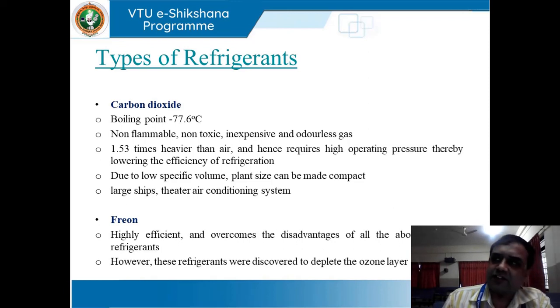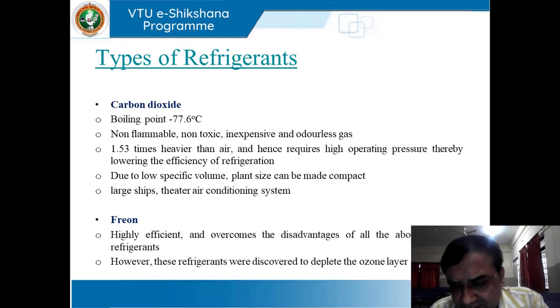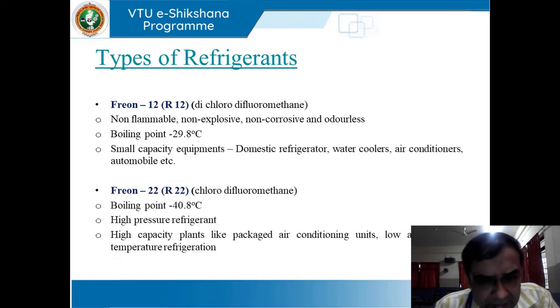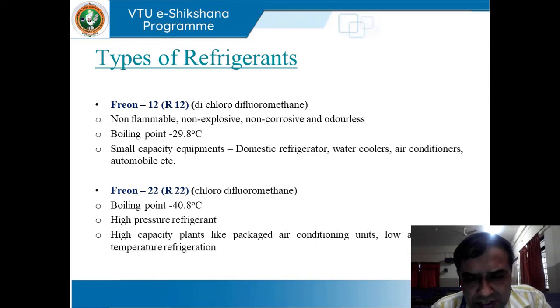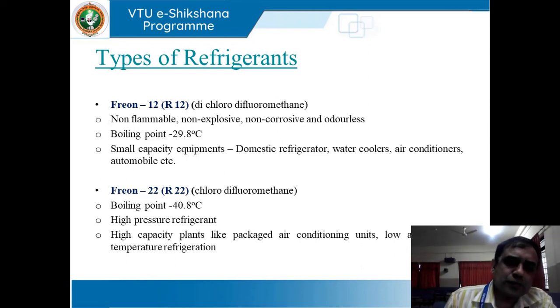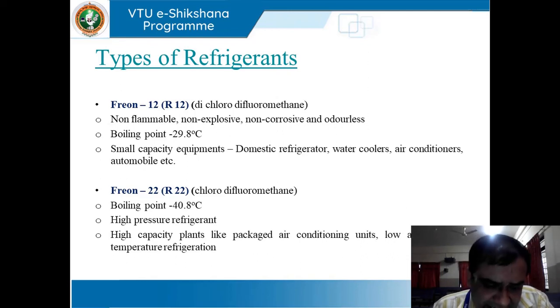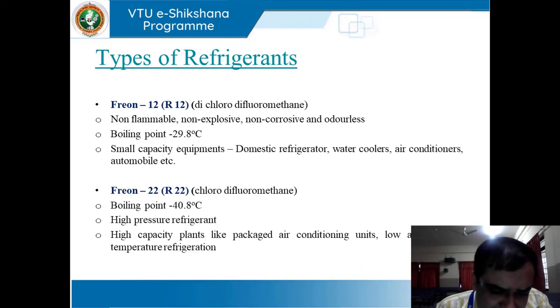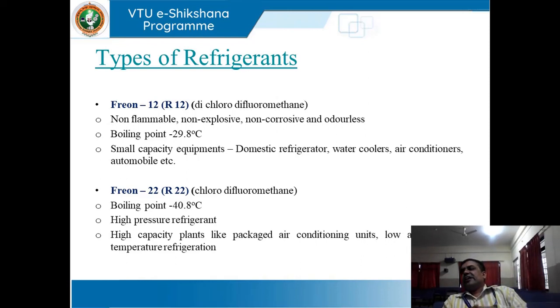Next comes Freon — one of the favorites for present-day researchers. Freon 12 and 22 are highly efficient and overcome the disadvantages of all above types of refrigerants. However, these refrigerants were discovered to deplete the ozone layer. Freon 12 has a boiling point of minus 29.8 degrees centigrade, and is non-flammable, non-explosive, non-corrosive, and odorless. Freon 22 has a boiling point of minus 40.8 degrees centigrade and is a high-pressure refrigerant, employed for high-capacity plants, packaged air conditioning units, and low and medium temperature refrigeration.